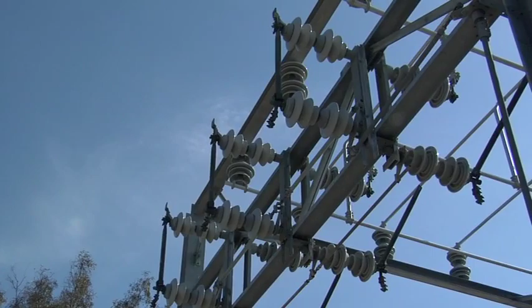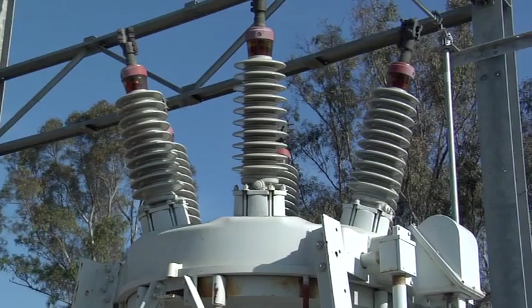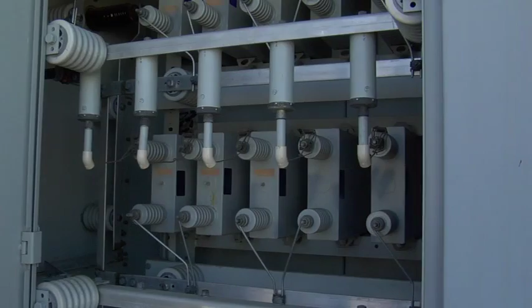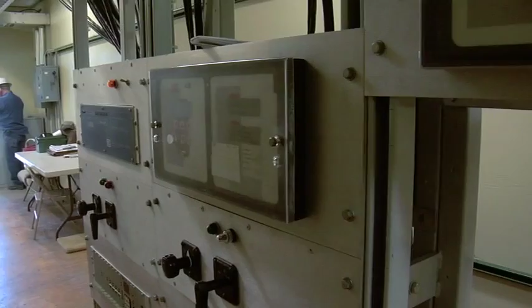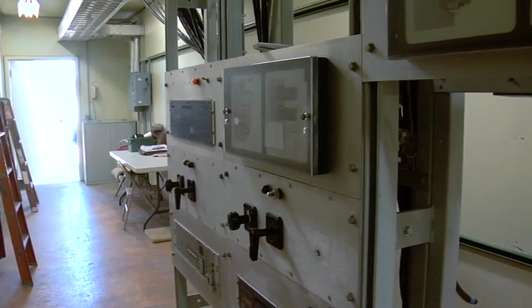When you go into a substation, you'll see a lot of different equipment and pieces. Maybe they aren't all familiar, maybe they are. What you'll come across typically are things like breakers and disconnects that we use to open and close switches, much like a wall switch in your home. You'll find transformers that raise and lower the voltage as needed in the community. And you'll also find things like old capacitor banks and reactors. One of the things you'll find in almost every substation, though, is a control house and a battery room. Both of those have both communications and control circuitry in it to make the substation work properly.